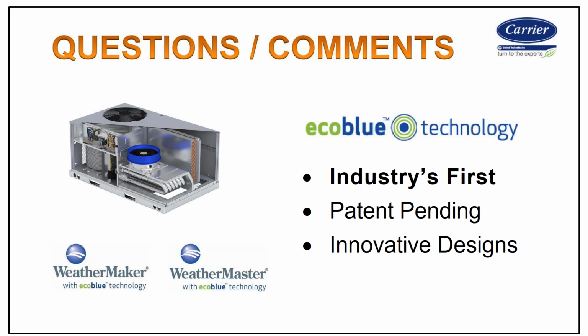All right. Steve actually has a comment that you probably can address. When checking for proper rotation on three-phase units, you cannot depend on looking at the fan in these units. You got to check the compressor rotation. That is 100% correct. So any ECM motor or VFD bearing unit will always have a correct rotation, provided it's programmed right, will have correct rotation of that motor.